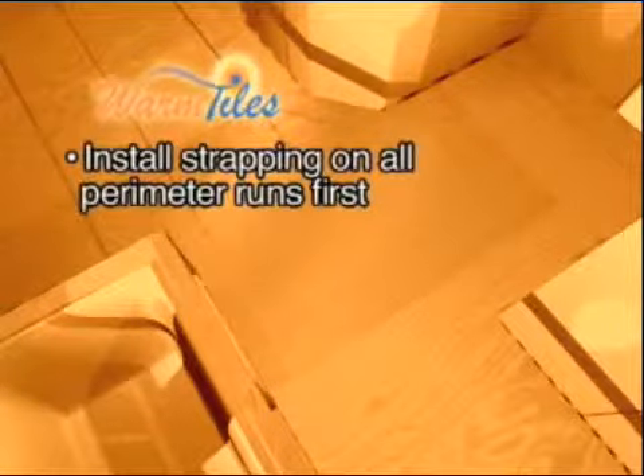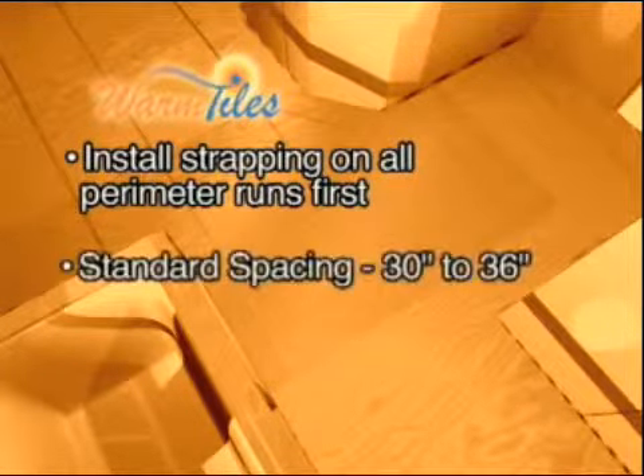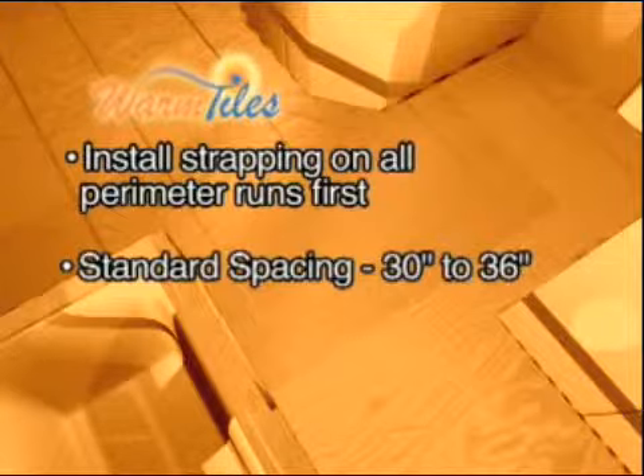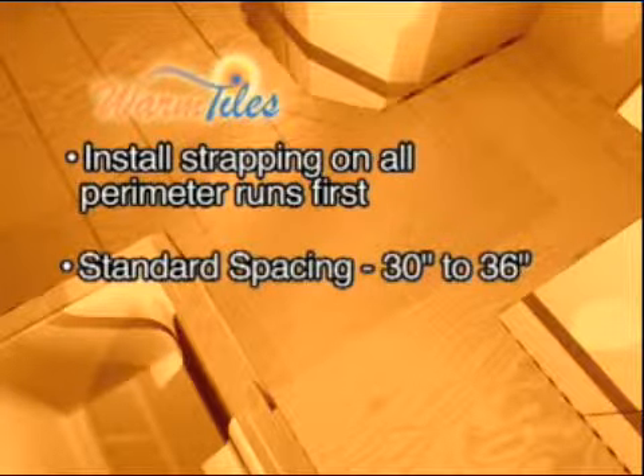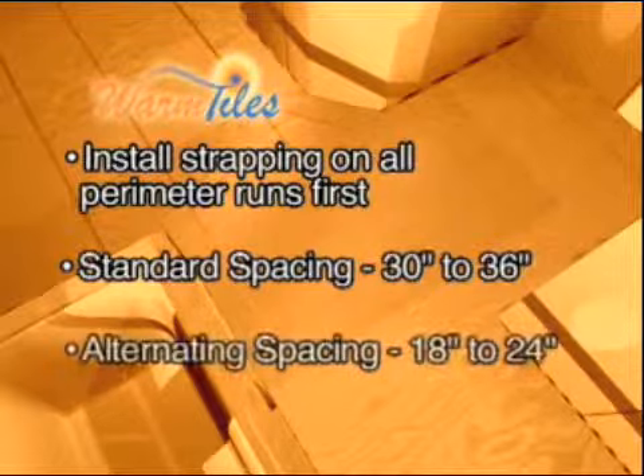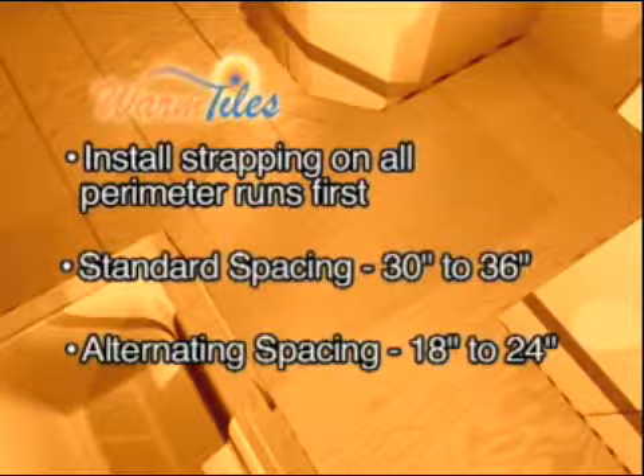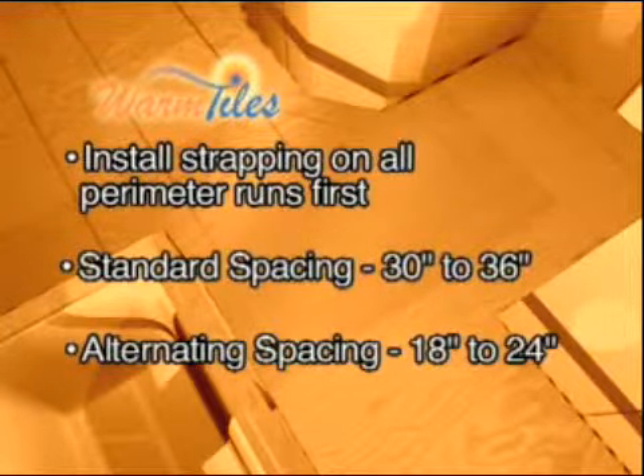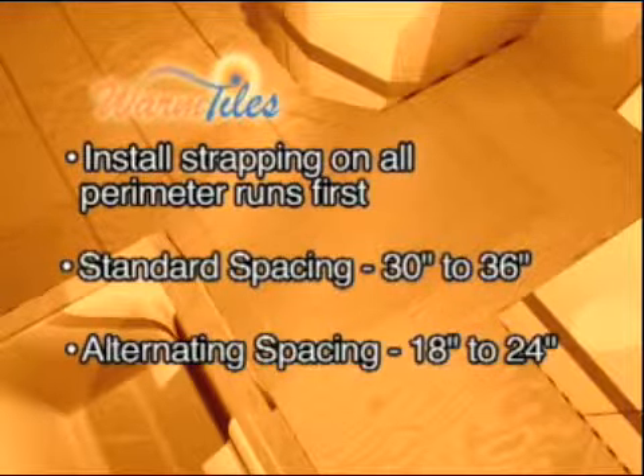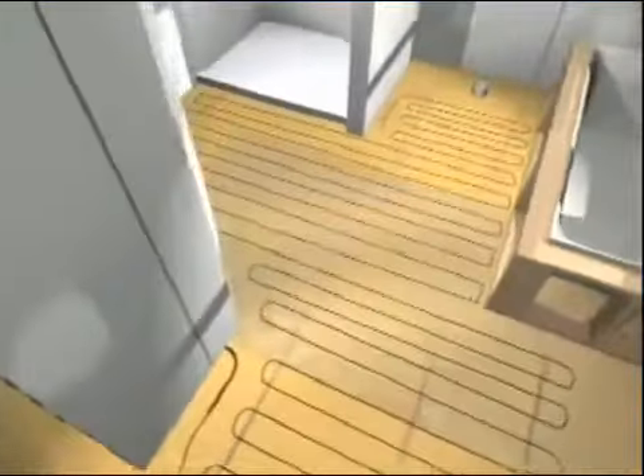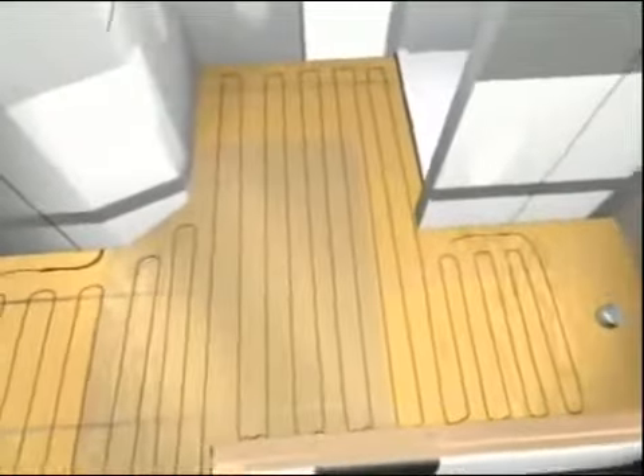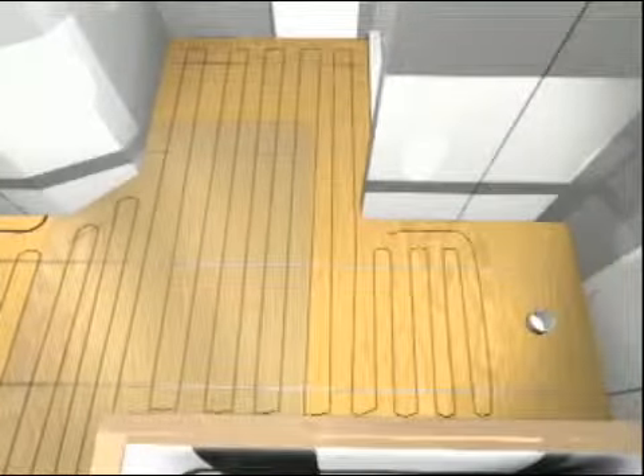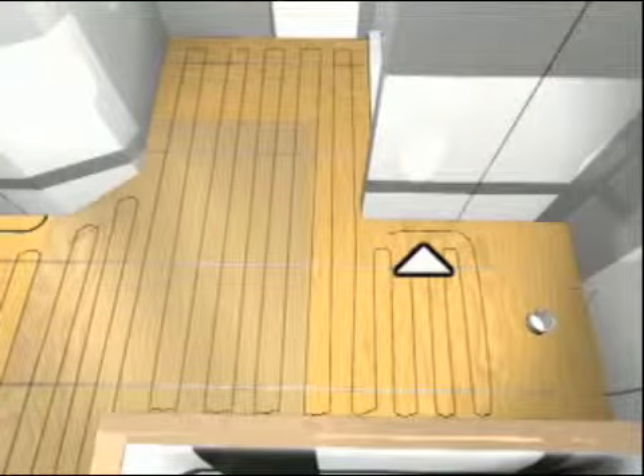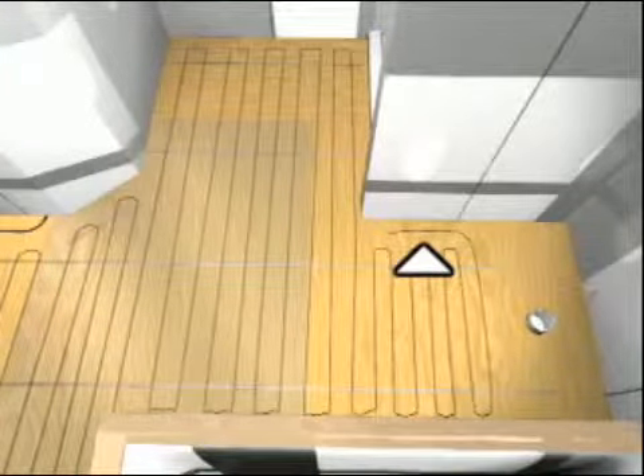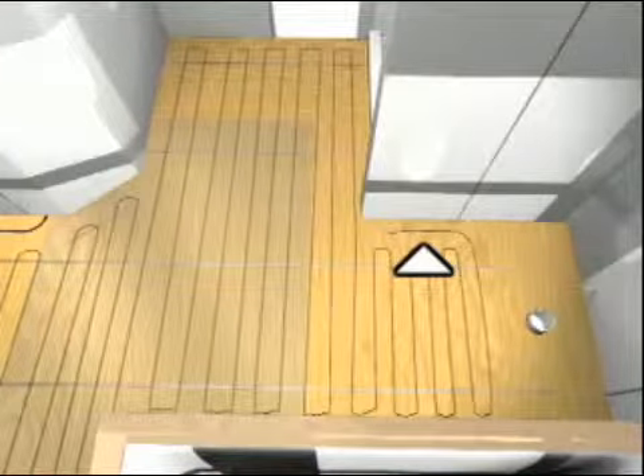Install strapping on all perimeter runs of the room first. For standard spacing, install subsequent runs of strapping at 30 to 36 inch intervals between the perimeter runs. For alternating spacing, install subsequent runs of strapping at 18 to 24 inch intervals between the perimeter runs. Then sketch a cable layout that corresponds to the strapping layout. Plan for the cable layout to end in a low traffic area or allow a 3-inch channel at the edge of the cable installation back to the low traffic area to route any excess heating cable there.